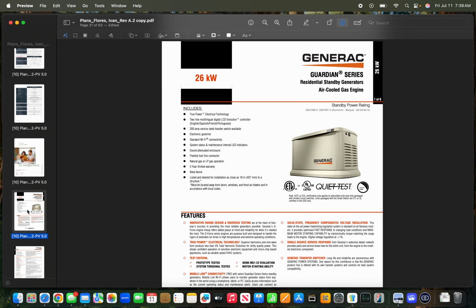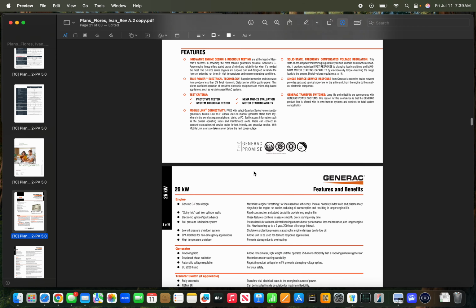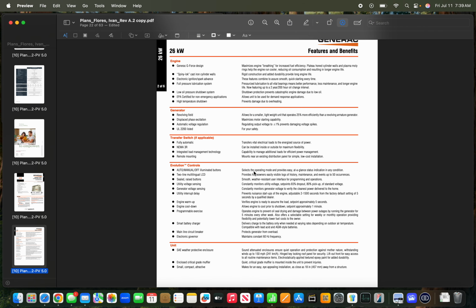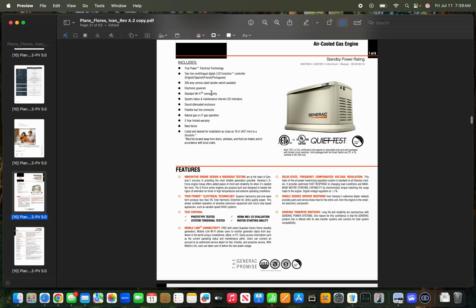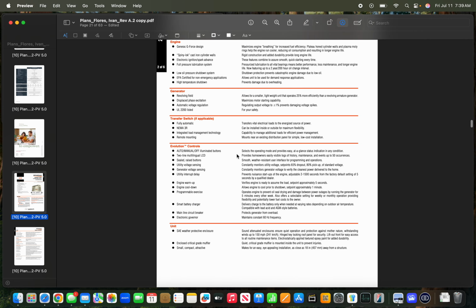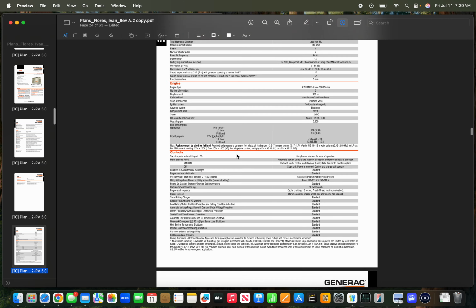Now, for the generator we went with Generac. There are other units available, but this is an air-cooled gas generator, liquid propane or natural gas, comes with a 5-year limited warranty. We went with the bigger unit, 26 kilowatts, because we're splitting the power between both sites, so we wanted ample power to power the homes and keep the batteries charged. The Generac is a pretty good generator in my opinion. You have to do your regular maintenance, but it typically has standard Wi-Fi connectivity so you can check on the system. It does its monthly cycling start, turns on, shuts off, it's pretty straightforward for having a generator on site.